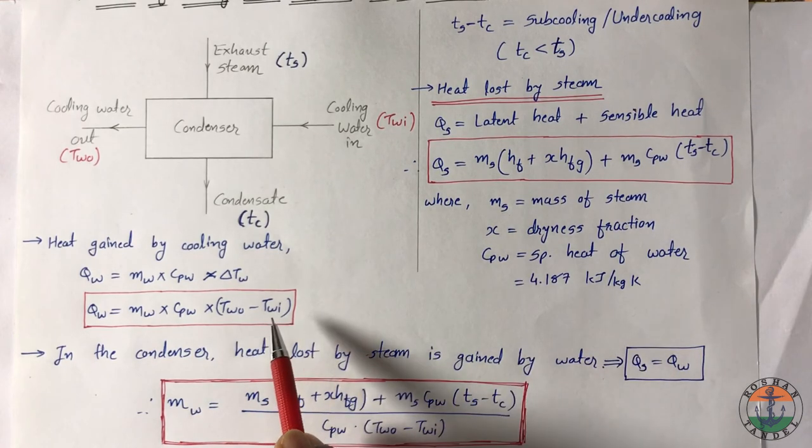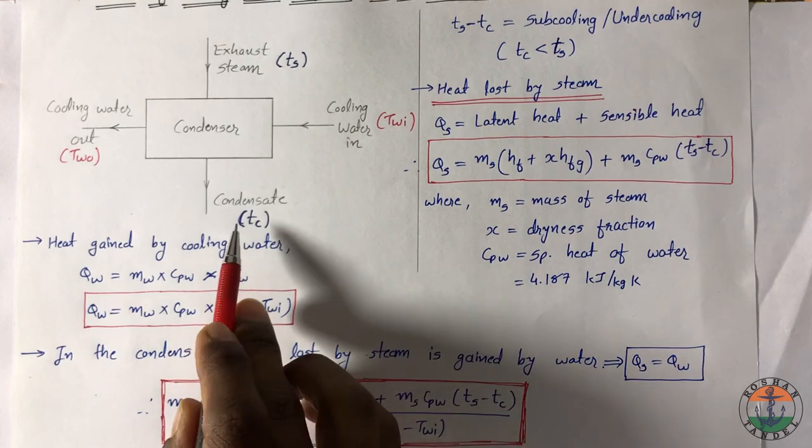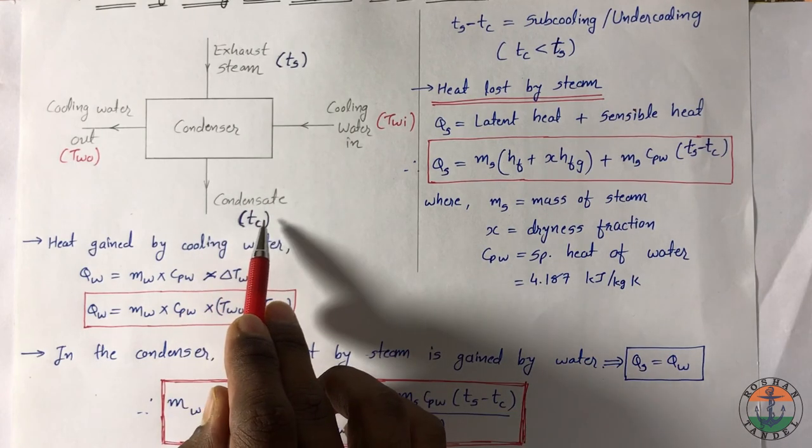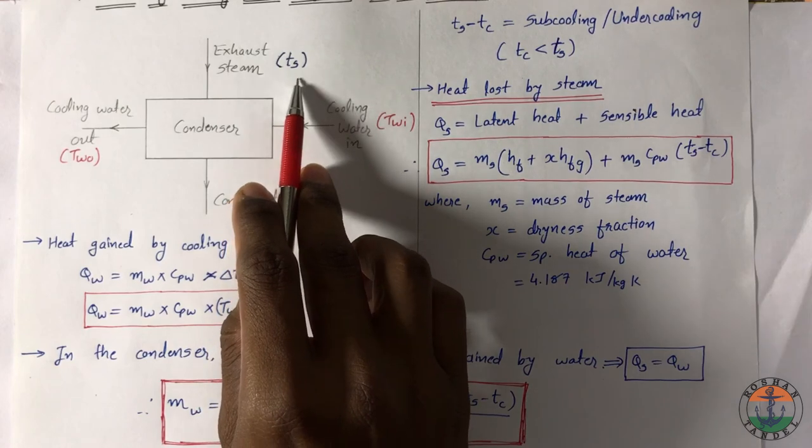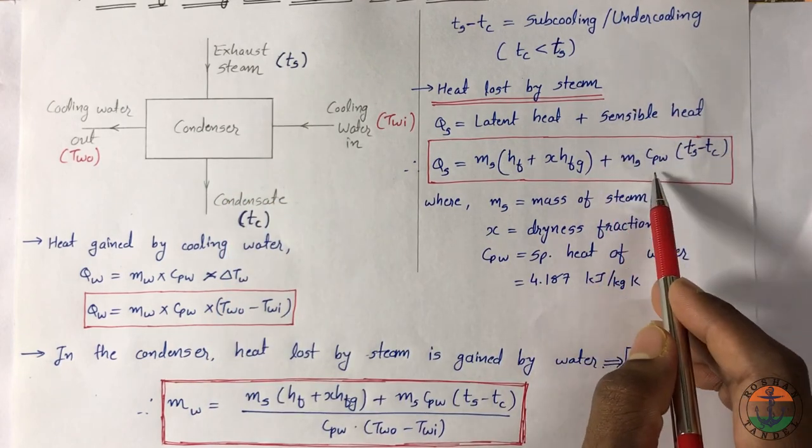Now if you consider energy balance as Qs is equal to Qw, mass of water can be calculated by this equation. If there is no subcooling of condensate, then output temperature will be equal to Ts. So here sensible heat component you have to neglect, keep using the latent heat component.